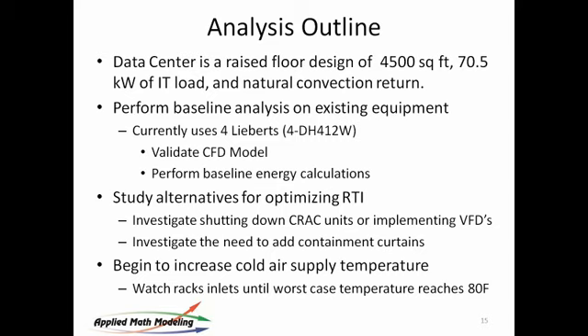And this particular model is a fairly straightforward data center. This one's DX based. So our ability to move the RTI number a long distance gets constrained by the fact that they're DX units themselves. But this is a very typical data center, and this is a real live data center, a colo that agreed to allow me to use their data center for analysis purposes here today. 4,500 square feet. Now, this is also very typical, is what they often do is build it for worst case analysis. I believe these are 30-ton units roughly, 30-ton CRACs. So they've built this thing for, and the kilowatts there is really 412. So they've built this thing for 1.6 megawatts of total load, and they're running it at 70.